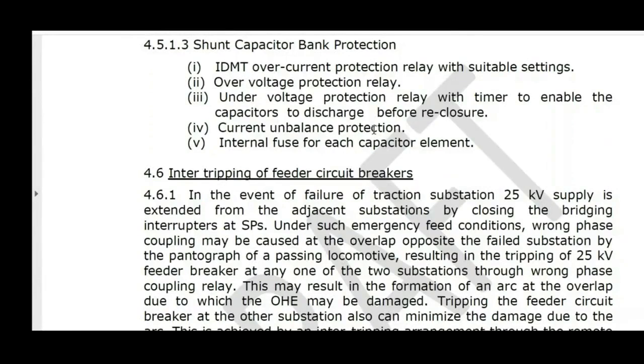The capacitor bank would be on 3-phase. So when an unbalance is created in the RYB, it will be able to identify. In case of single phase systems, it is the current unbalance before and after the system. Internal fuse. This is like the fuse failure which we have already seen. If the fuse fails, then your capacitor value actually comes down. So therefore the fuse also has to be identified properly.